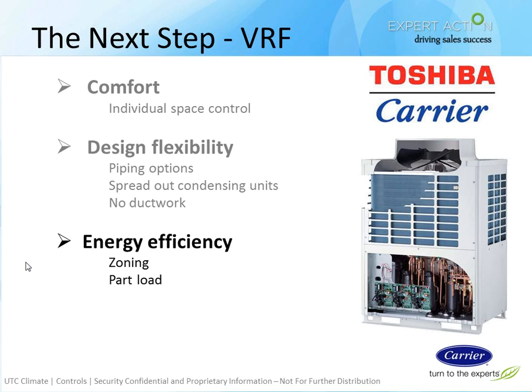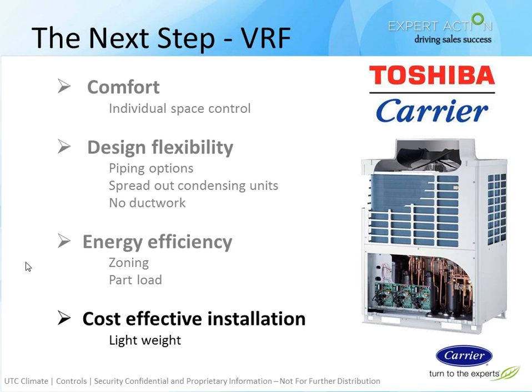Energy efficiency is very good with these systems. You get great zoning with this. This is probably the best zoning you can get because you just deliver the amount of refrigerant to the unit that's needed to carry the heat away or deliver heat as needed in cooling and heating mode respectively. Another way that we achieve great energy efficiency is in part load situations, with all the compressors in these units being inverter controlled. They ramp up to their most optimal operating level and operate there, providing the greatest efficiency, quiet comfort as well. And it can be a very cost-effective installation because the indoor units are lightweight. The outdoor units are, of course, pretty heavy, but the indoor units are relatively light, consisting of high-wall units, ceiling cassettes, smaller ductable units, and ceiling suspended.